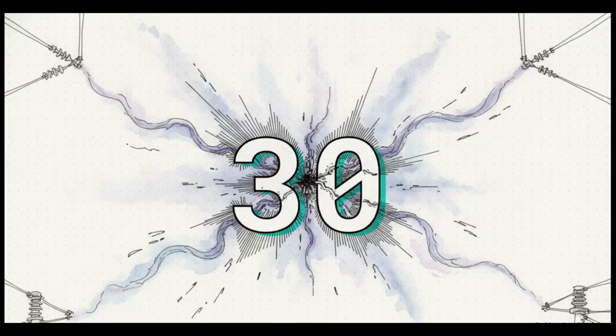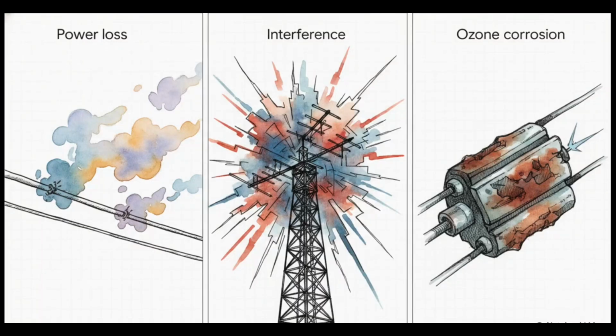And this breakdown doesn't just happen at random. It happens at a very specific mathematical threshold, 30 kilovolts per centimeter. When the electric field exceeds this peak at standard temperature and pressure, the air just gives way. The electricity literally leaks out into the surrounding atmosphere, and that is what creates that faint bluish-purple aura we call corona discharge. So it looks kind of cool, right? But it's definitely not just a pretty light show. The operational impacts here are severe.